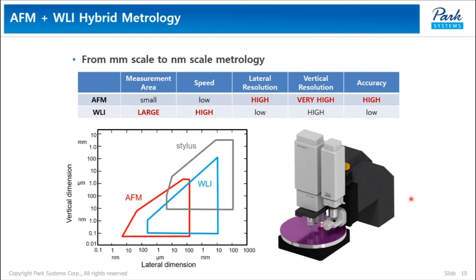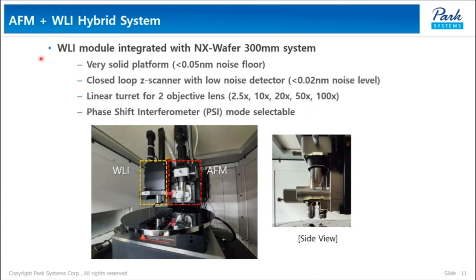Therefore, we think these two technologies complement each other very well. The WLI module is integrated with the NX wafer 300 mm system, which is Park's best seller in the semiconductor industry. The NX wafer has a very solid platform with less than 0.05 nanometer noise floor, and the WLI module is also equipped with a closed-loop Z scanner with a low-noise detector used in AFM to guarantee the best performance. In addition to conventional WLI mode, PSI — phase shift interferometry mode for high-resolution imaging — was also equipped.